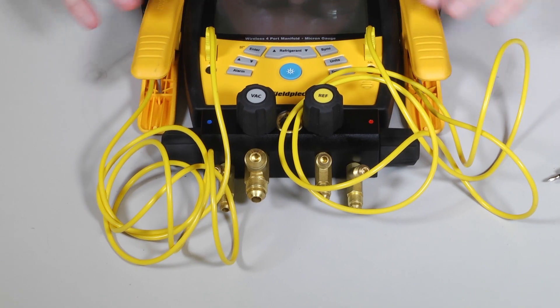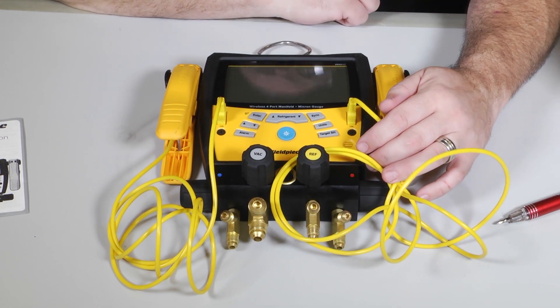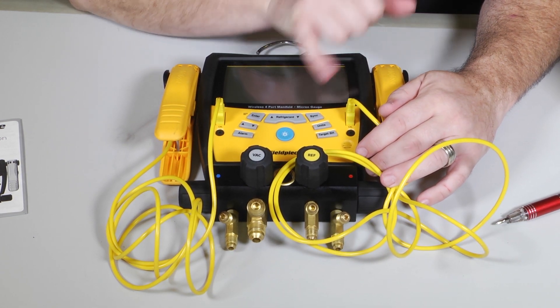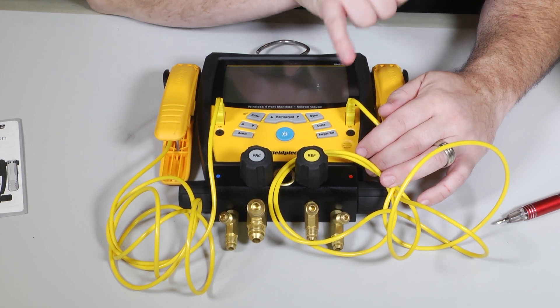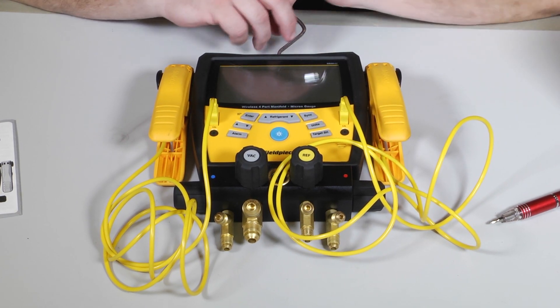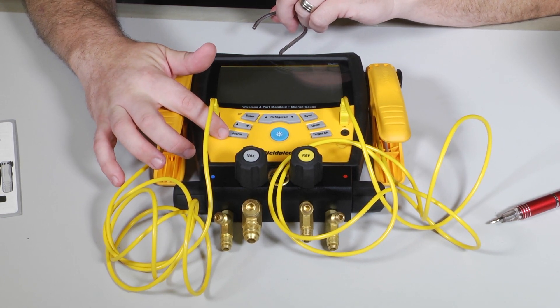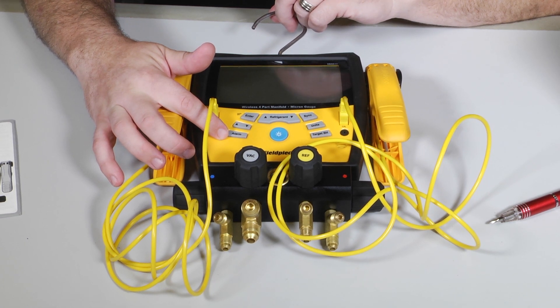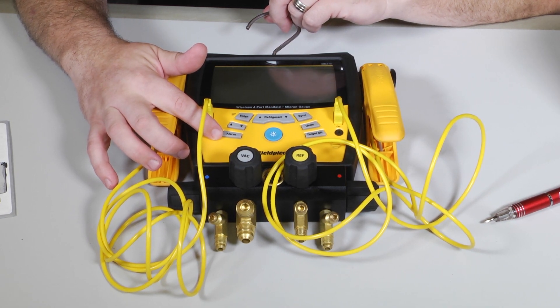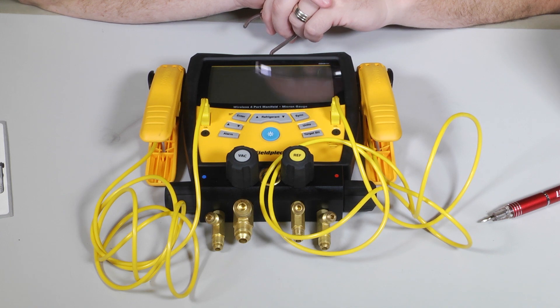It has over 45 refrigerants pre-programmed into it. It has the ability to sync with their Job Link platform, so if you have other Fieldpiece wireless devices you can collect data directly from them to your Job Link and sync them to your S-MAN 460. It has the ability to change the units that you want to read, set target superheat for fixed metering device systems, and since this has a built-in micron gauge it has two alarm levels you can set — one for your low level alarm to let you know when you've hit your vacuum range, and a high level alarm for your decay test if your micron level rose higher than it should have. Note that it doesn't come with its own hoses, so you will need to supply your own.